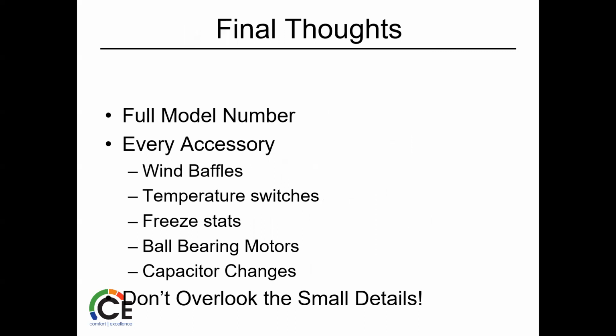So again, when you're looking at one of these, full model number, every accessory, some need wind baffles, depends on the unit, depends on the application. If you got a good false wall or something, maybe you don't need to worry about it. Temp switches, freeze stats, ball bearing motors, at times you're going to need it. Sometimes capacitor changes. Those are those little things that, oh, I just need to make this run, but it's not going to operate.